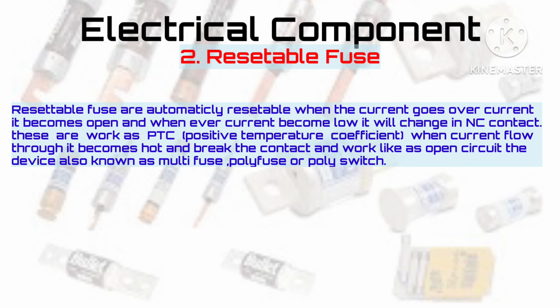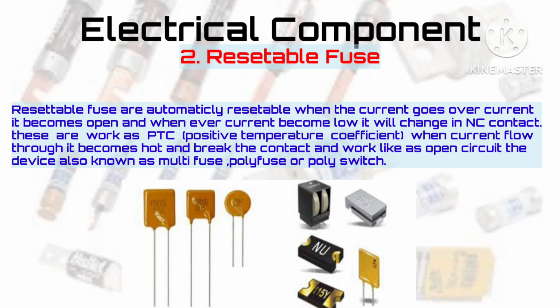Resettable fuses are suitable where frequent overcurrent conditions occur or constant uptime is required, such as overcurrent in consumer circuits, electronics PCBs, power lines like SMPS, telecommunication, signal conditioning and process control. This fuse has the property to reset automatically when the temperature becomes low or comes under control.